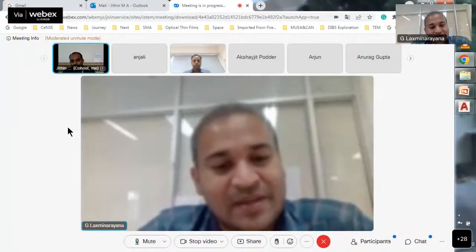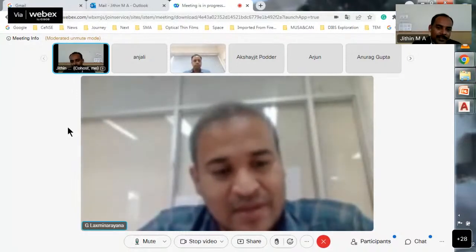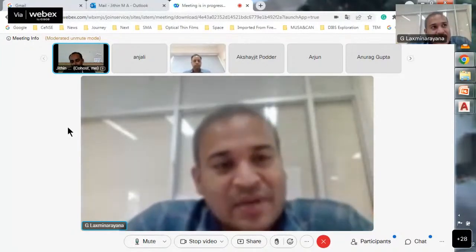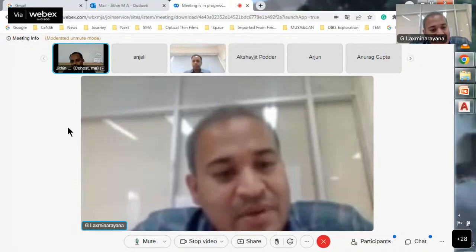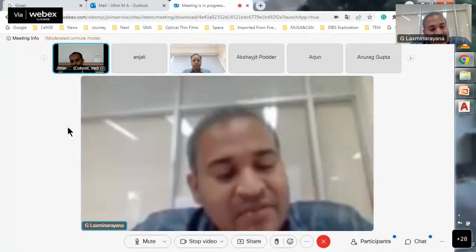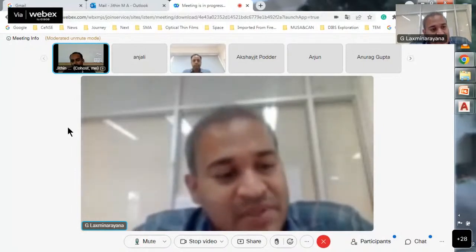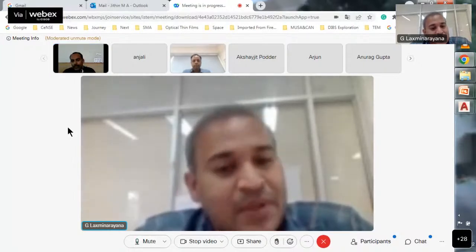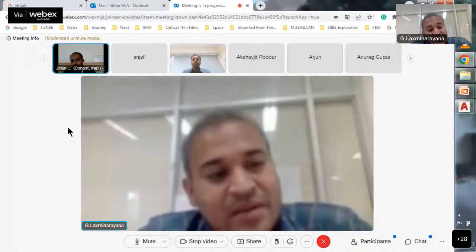Yeah, we can do that. I have done that once with our industry partner. And for leak detection, whatever our helium MSLD leak detector gives, let us say ultra low leak, 10 power of minus 7 or minus 9 millibar liter per second, is there any conversion from this machine leak rate to the general leak rate we do for a pressure system and the pressure drop per time? Is there any calculation available to correlate the leak rates?